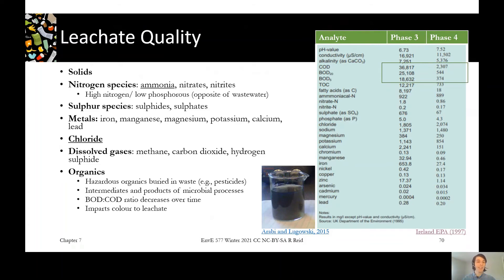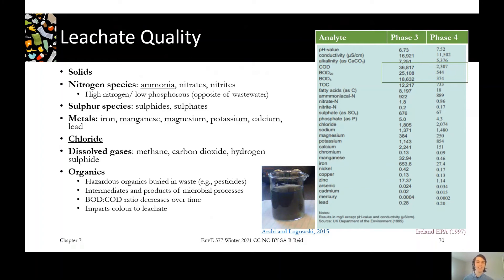Chlorides are often very high in leachate, and that's important because chlorides we can't really destroy with any treatment technology — they need to be filtered out with reverse osmosis or the leachate would need to be distilled to remove them, and that's an important parameter for our receiving body because we don't want to fill it full of salt. Dissolved gases might also be present in our leachate, which are important for health and safety in our leachate treatment systems. Often the leachate system will be connected to the landfill gas system to pull off gas that's off-gassing out of the leachate and prevent it from building up in places where we don't want it.